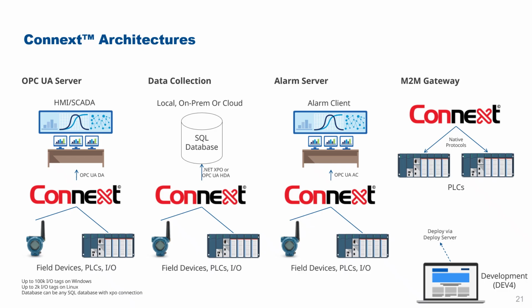You can use Connext as an OPCUA server, so we can take data from field devices, PLCs and I/O, bring that into the Connext server, and make it available via OPCUA using the data access specification. That's ideal if you've got a remote application such as an HMI SCADA or a database that can do OPCUA data collection, and it can use Connext to convert all those PLC protocols into a common OPCUA protocol. That OPCUA protocol can also be signed and encrypted using certificates for secure communications.